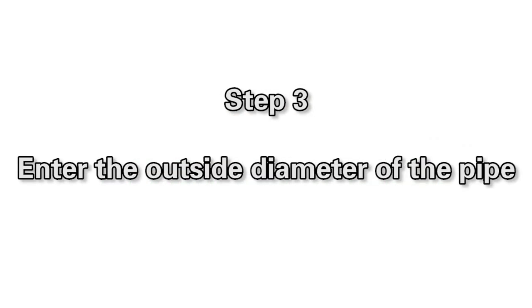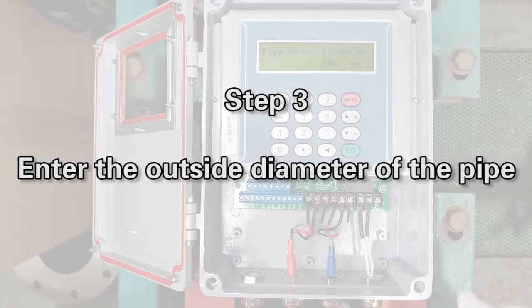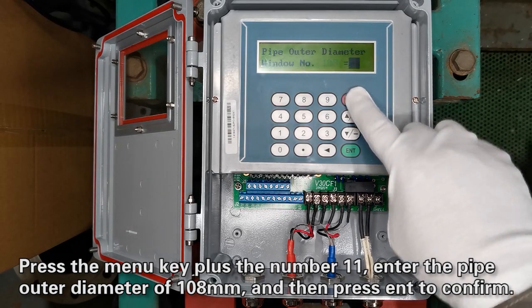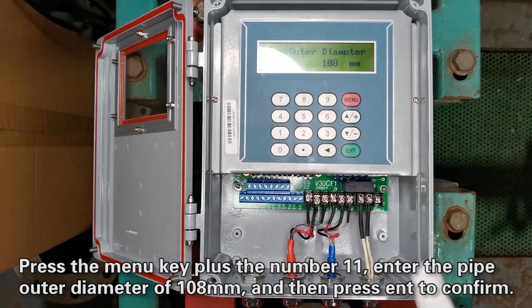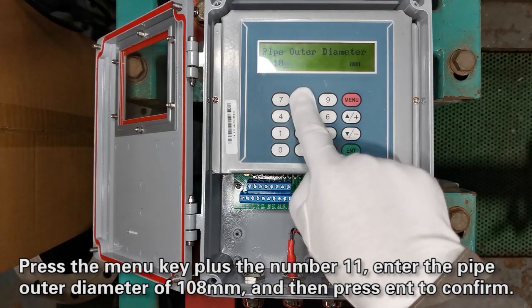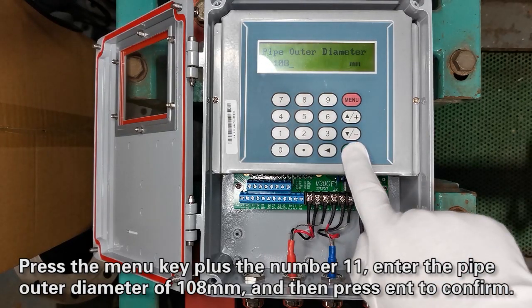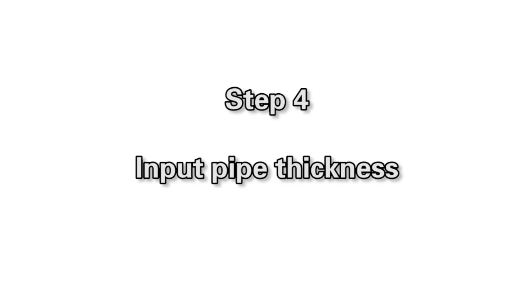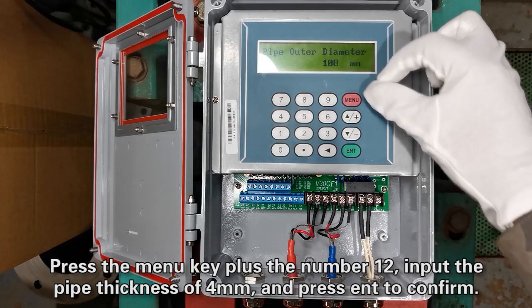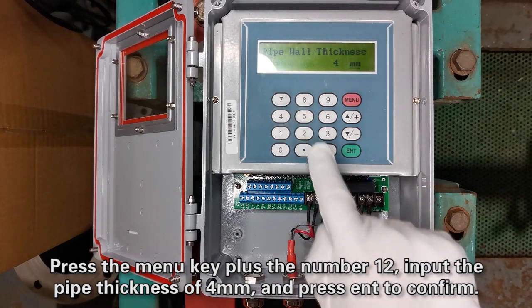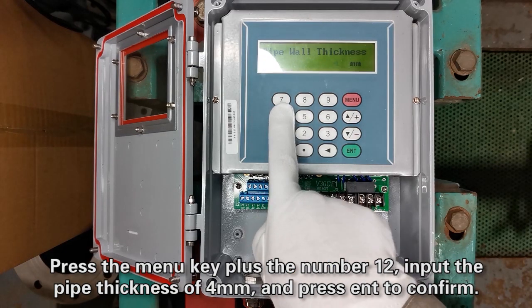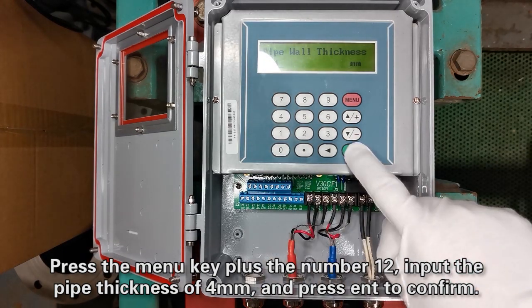Step 3. Enter the outside diameter of the pipe. Press the menu key plus the number 11, enter the pipe outer diameter of 108 mm and then press Enter to confirm. Step 4. Input pipe thickness. Press the menu key plus the number 12, input the pipe thickness of 4 mm and press Enter to confirm.